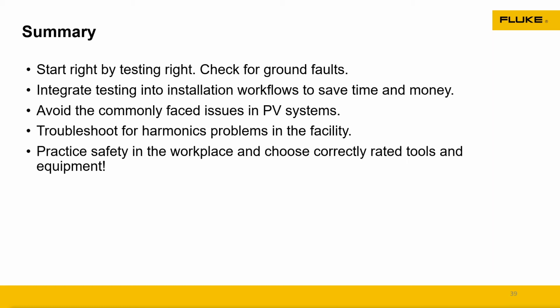Do that dead-live test on that. Having power quality units is going to help you troubleshoot those harmonic problems that could be out there. And again, just practice safety in the workplace, that's the key win on that. Use the right PPE for the right jobs, use the right meters for the right jobs. Part of my safety session is that the meter and test leads are an extension of your PPE, so we want to make sure those tools are rated correctly for being out in the field.